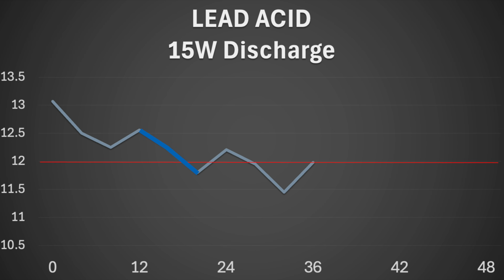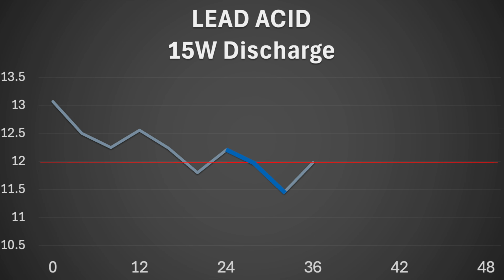24 watt hours is drawn without drama. On the third go, the voltage under load drops down below 11.5 volts, which at modest current is rather low. I stop and let it rest. We end up measuring just under 12 volts, which is the point at which our internal alarms go off to say stop discharging a lead acid battery. I'll add a red line on the charts to show the subjective level at which we should start worrying about load voltage for each battery chemistry's long-term health.